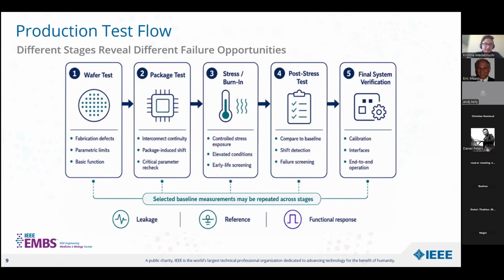Then we have to perform a pre-stress measurement to have a baseline. The device goes through burn-in afterwards, which is maybe a high temperature soak for like 24 to 48 hours. This is a controlled way of stressing the part and accelerating the failures. Afterwards, the selected measurements are repeated to see if there's any meaningful shift that might have been accelerated due to this burn-in operation. And then at the end, we have this final functional test. We evaluate the complete product configuration, we ensure that we calibrate any variation, and we test our end-to-end operation.